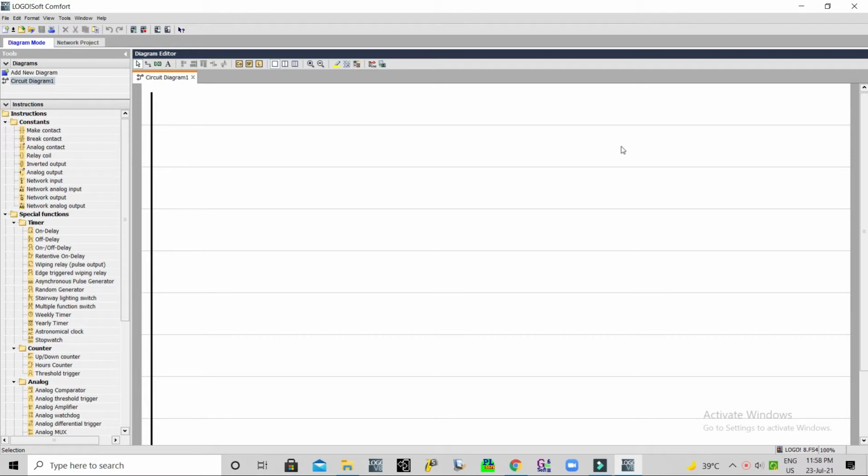Out of 3 ACs, 2 ACs will be running as duty and 1 AC will be standby. The 2 running always cycle on a time basis, so 1 and 2 will work, then 2 and 3, then 3 and 1, while the remaining one is in standby mode. If any AC fails and the temperature increases, then the standby AC will run to maintain the temperature in the data center. Today we will see how we can make this 3 AC control program.